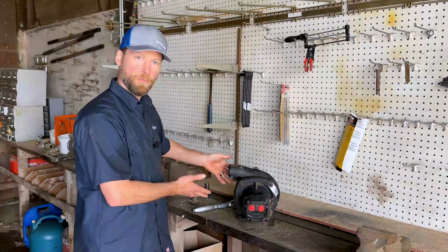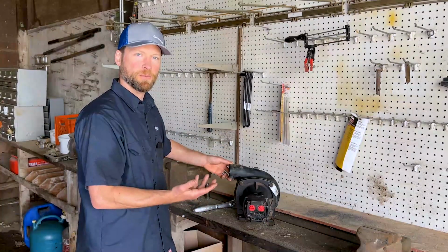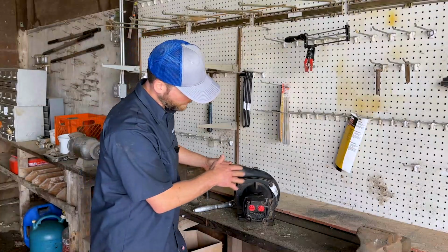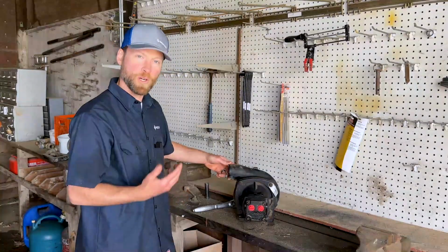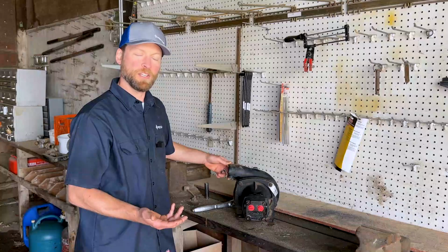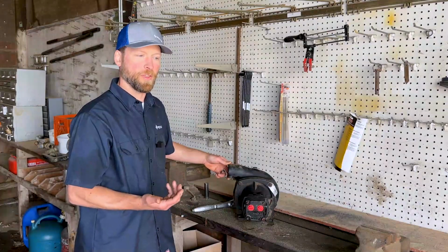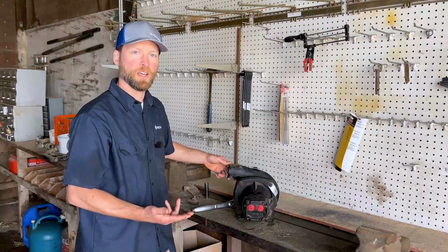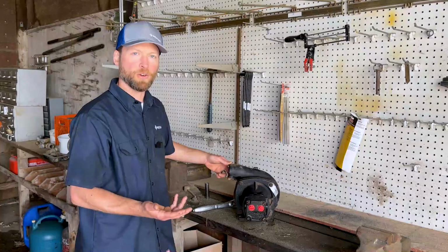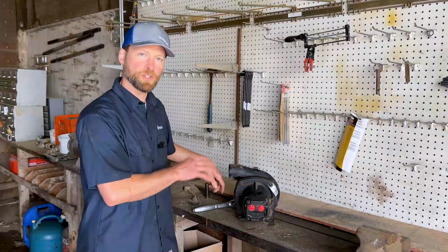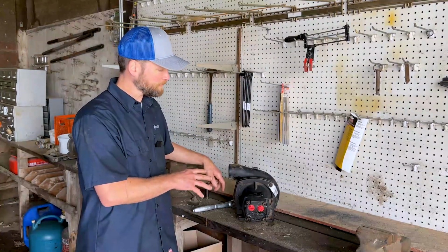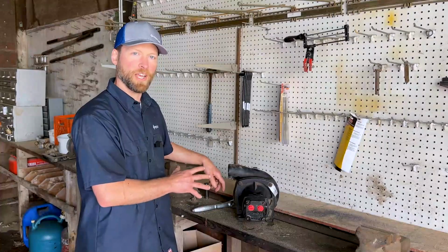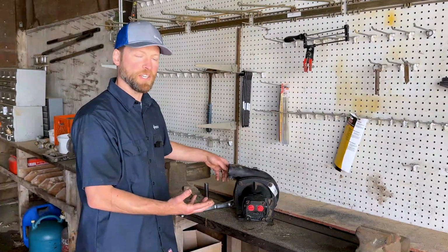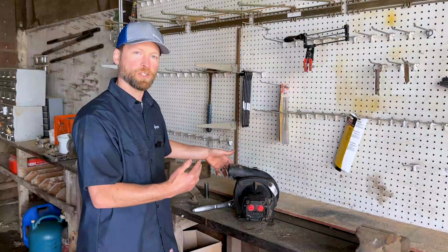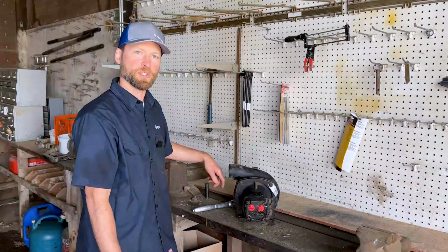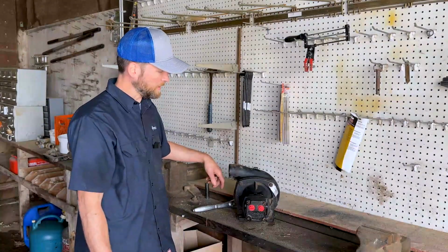So now that we've got the ForceField pump installed on the machine, we wanted to take a look at the customer's old pump, tear it down, take a look at some of the components. I'm looking at the date code on the label. It appears it's from 2010, so it's got about 14 years of use on it. But I should note that the customer's put in 2 seal kits. They've also replaced the impeller over the years. So there has been some service and maintenance done to this pump, but I want to open it up and take a look at the internal components and see what might be causing that lower pressure or that decreased performance that the customer is seeing. So I'll tear it apart and let's see what we find.